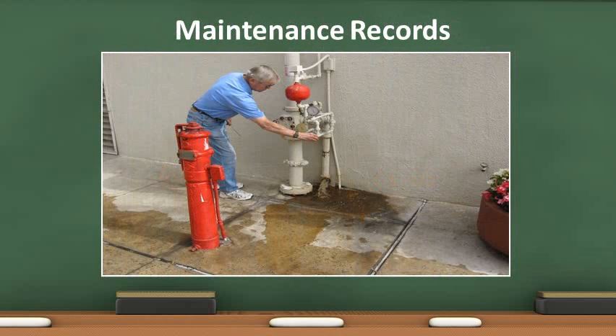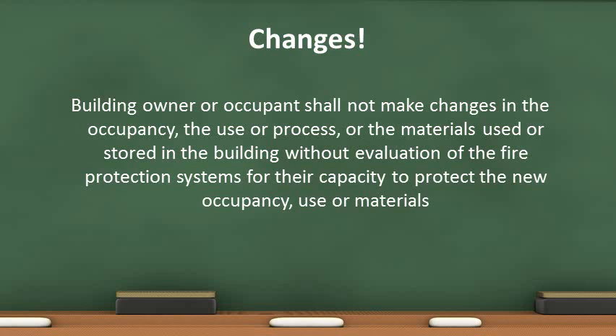Periodic maintenance is required on all components of the sprinkler system. Monthly, quarterly, and annual inspection, testing, and maintenance, as well as 5-year certifications are required on all fire sprinkler systems. Records of testing and maintenance must be kept on site. If the fire, materials stored within the structure, the use of the structure, or processes or materials within the structure change, the fire protection system in the building will need to be re-evaluated and changed as necessary.